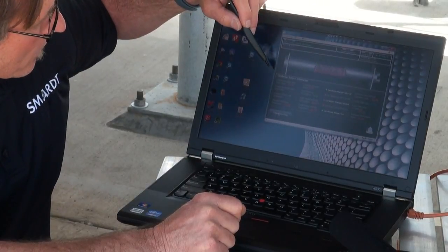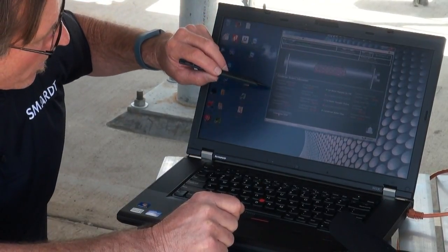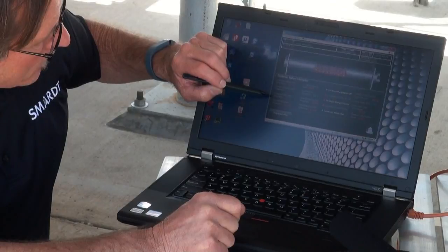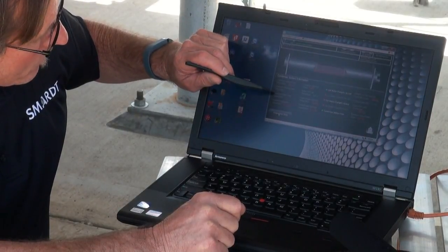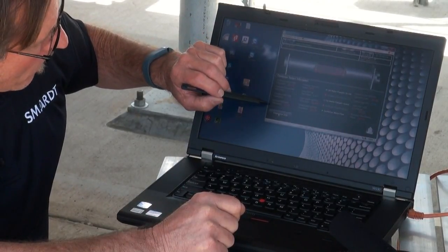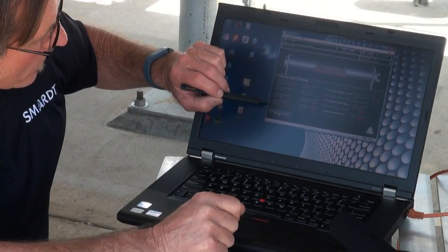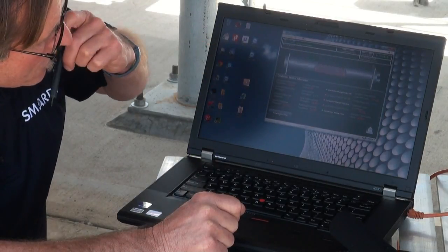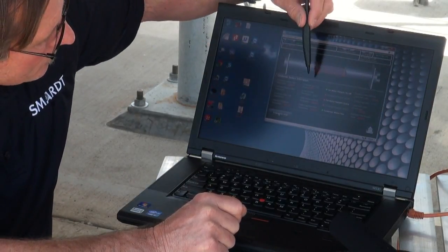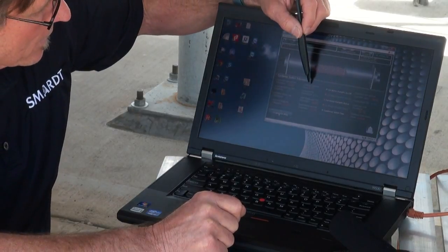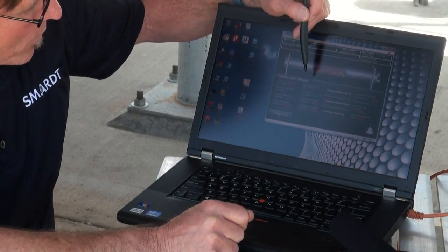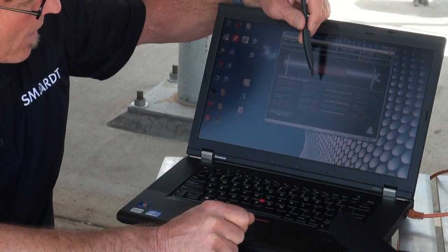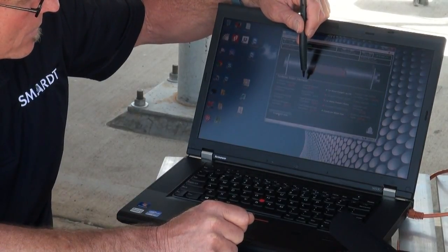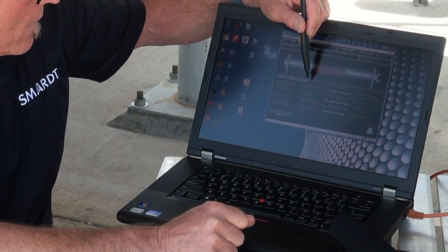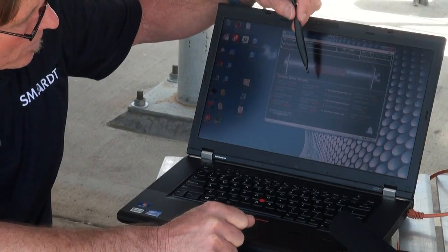We've got condenser leaving water, condenser entering water, delta T, which is our difference in temperature from entering to leaving. We've got saturated refrigerant temperature. We've got our approach temp. Again, that approach temp is a little higher than the evaporator.